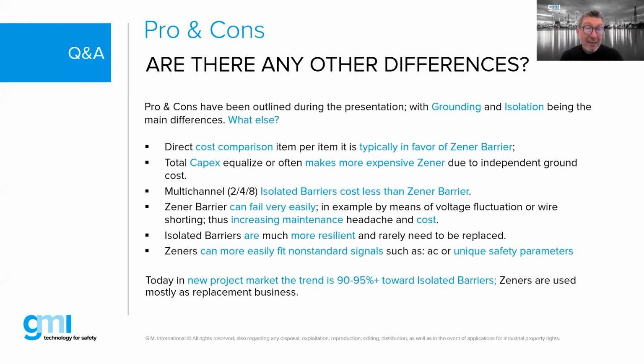We also have size to consider. There's one instance where the Zener barrier really takes the advantage over isolated barriers. Isolated barriers have their own disadvantages. Because they're an isolator, they need to be specifically designed for that application. So if you want 4-20, you need a 4-20 milliamp barrier. You cannot use a DI barrier in a 4-20 loop. It will not work, because there is electronics in it. You take a 4-20, you digitalize it, you put it through the transformer, you recreate 4-20 and so on. A Zener barrier doesn't do anything. So it can be used in applications that you cannot find an isolated barrier for.